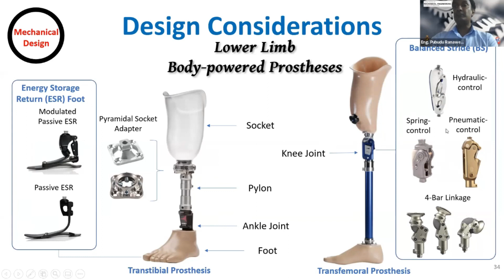When it comes to the knee joint, you have different types of knee joint to support the intricate motions of the knee. Typically, the biological knee does not rotate about a fixed joint axis of rotation. The axis of rotation tends to migrate as the knee flexes. So in order to support this migration of the knee rotation axis, a 4-bar linkage system has been adopted by most prosthetic lower limbs. You also have a different adaptation of the same technology in order to provide a certain amount of damping during the stance phase to provide balance control. You have spring control, pneumatic control, and hydraulic control damping methods available.